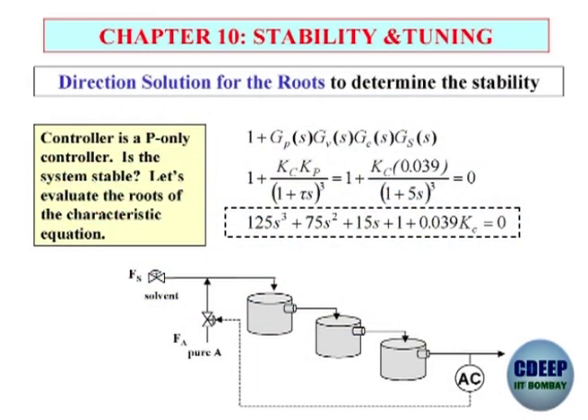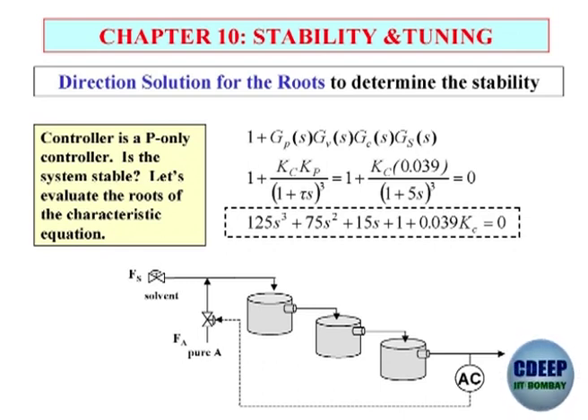That approach is not always practical because in practice you need transfer functions — the process transfer function, the valve transfer function, and the sensor transfer function. If you know all these pretty well, you can write down the characteristic equation and determine K_c. But when you are facing a big, complex plant, who will give you G_p, G_v, G_s? Because you do not have knowledge of these transfer functions, you go for an experimental procedure to determine K_c at the critical gain. That is why Ziegler-Nichols presented an experimental procedure — in practice with complex plants you cannot get the transfer function.